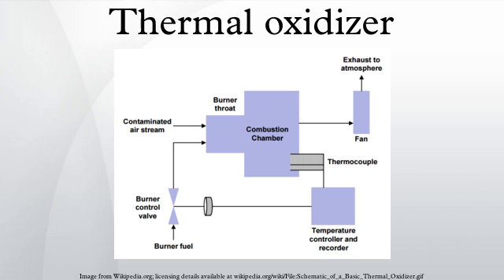The final temperature may be as high as 1100 degrees Celsius for applications that require maximum destruction. The airflow rates are 2.4 to 240 standard cubic meters per second. RTOs are very versatile and extremely efficient, and a thermal efficiency can reach 95%.